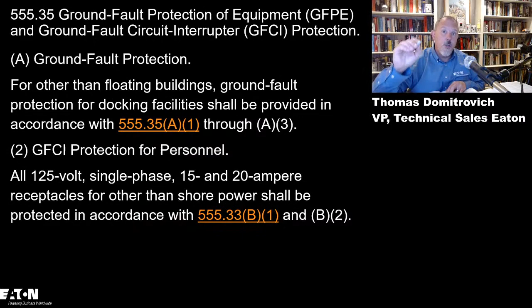All right, so I got to get back to where I was, and I don't know if I remember where I was here. All right, so that's in accordance with B1 and B2. So I just read both of those. B1 says receptacles in other locations, you need to follow 210.8, and anything that's other than shore power can be put on that pedestal, but it has to be marked not for use for shore power. So you can't power a boat. I don't know that you would power a boat off a 20 amp circuit, but that is for a different day.